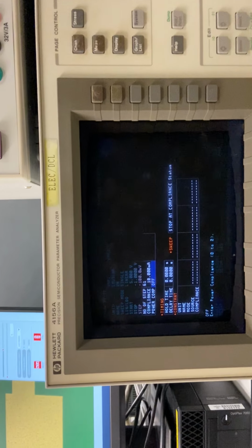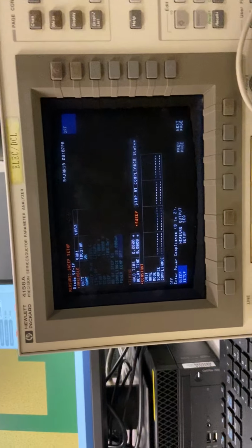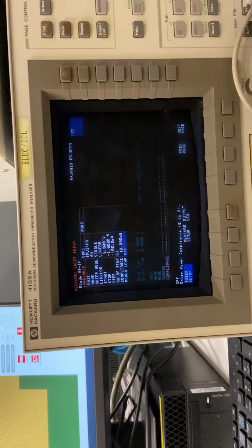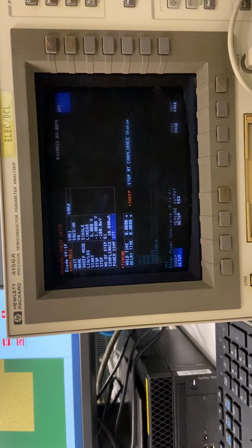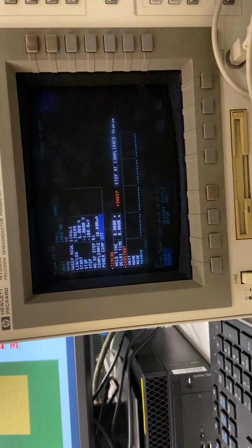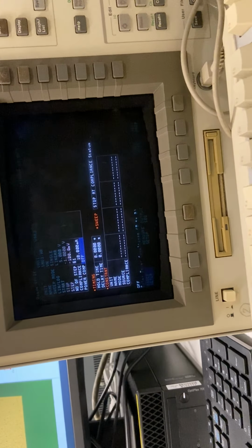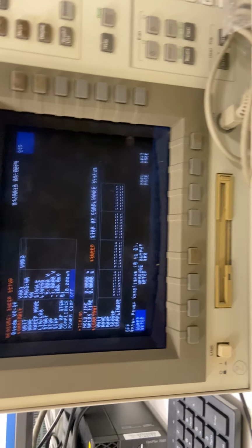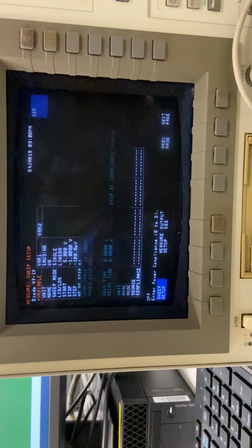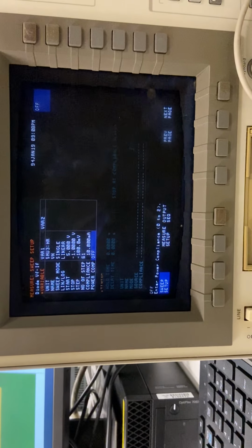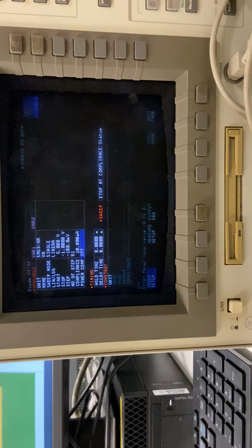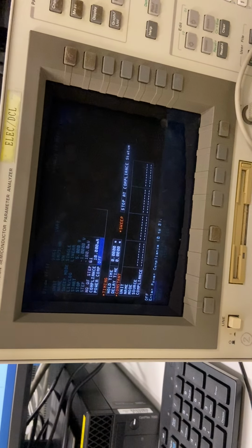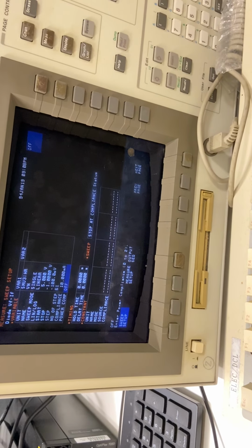If you look at this whole page, you will now see that whatever we have mentioned before, in terms of the scanning range, the step size, and everything, is there already. Is there anything that needs to be defined? The sweep mode: single. To use a single sweep, you choose the mode single. Single means from start to stop, and then after that the measurement stops. There's also double. If you choose double, then after the single direction, it returns from the end point back to the start point again.